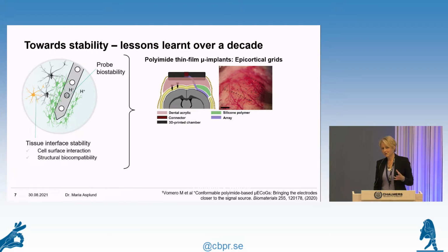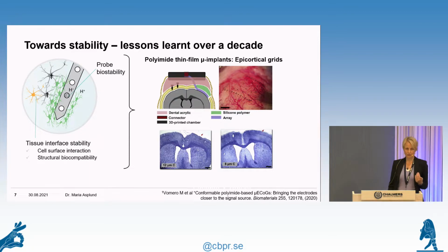So these epicortical grids, it's for another purpose, but it's a soft, flexible grid that is placed on the surface of the cortex to record superficial neurons. This is made in polyimide with platinum metallizations. And it's supposed to be able to record over many months and induce little scarring. That's the whole idea. And simply by changing the thickness of the polyimide, of the polymer construction material, from 12 micron to 8 micron, we can see, I don't know if you can see it here, I'll try to point it out. Here we see there is cortex depression with the thicker devices, but when we start to thin the devices down, we can see that because the device conforms to the brain curvature, there is actually very little scarring.